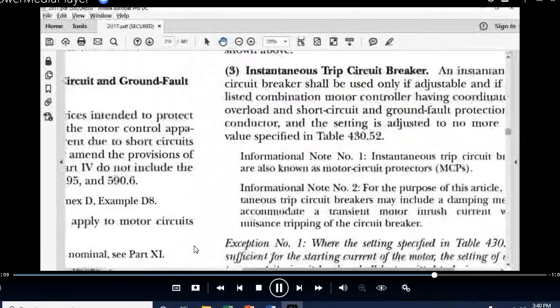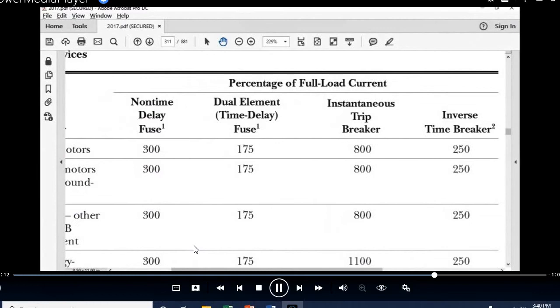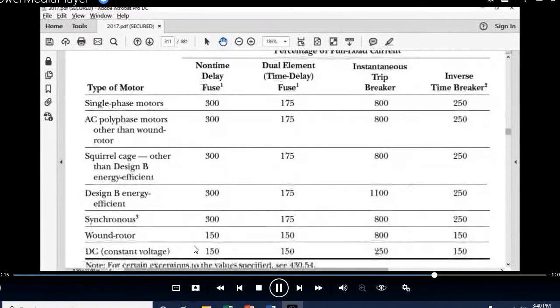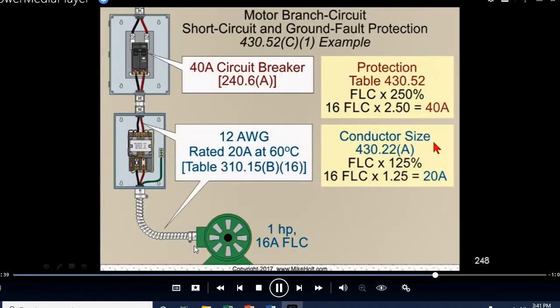Now we go to a table. And this table says inverse time breakers. You see here? They're all 250. We're not going to deal with wound rotor or DC constant voltage motors. So when you get to a breaker, you're going to use 250%. When you get to a dual element fuse, it's going to be 175. And when you get to a non-time delay fuse, it's going to be 300%. All my examples are circuit breakers, and circuit breakers are 250. So 16 times 2.5 gives me 40 amperes. I put a 40 ampere breaker on a 12 gauge wire.